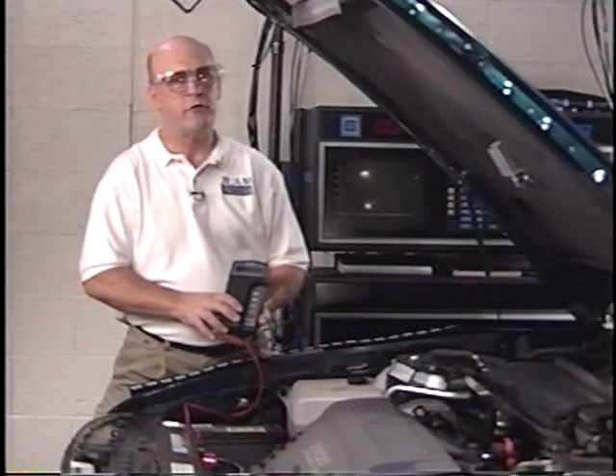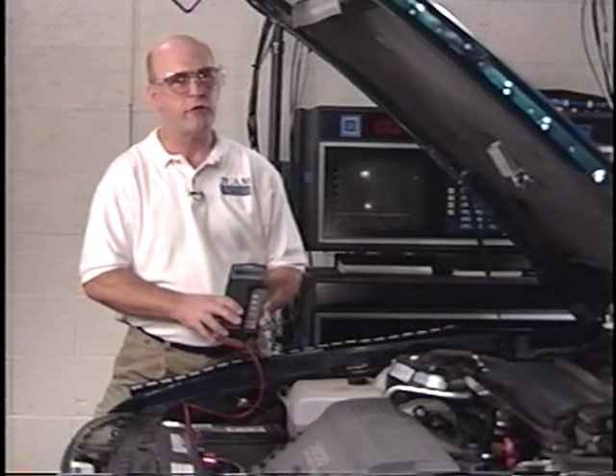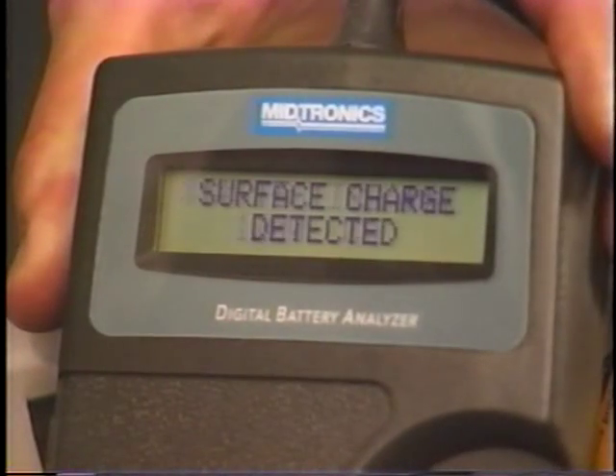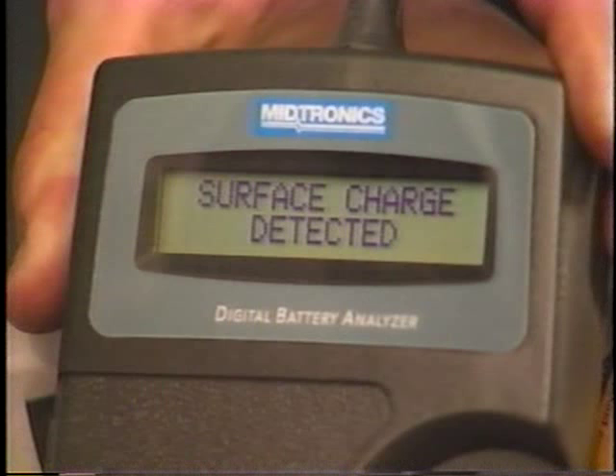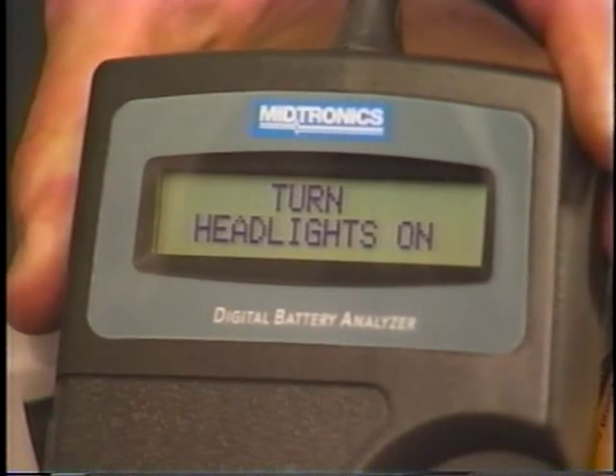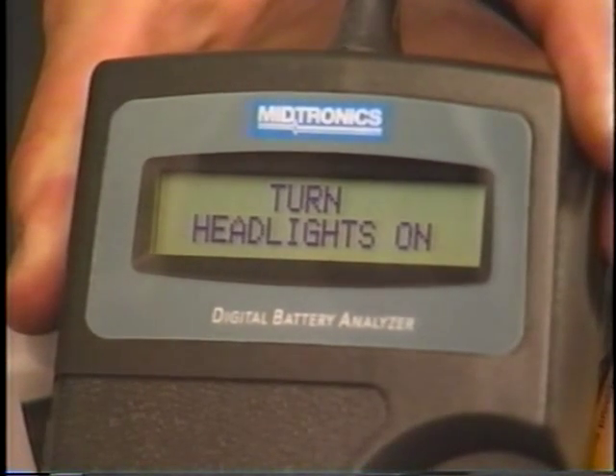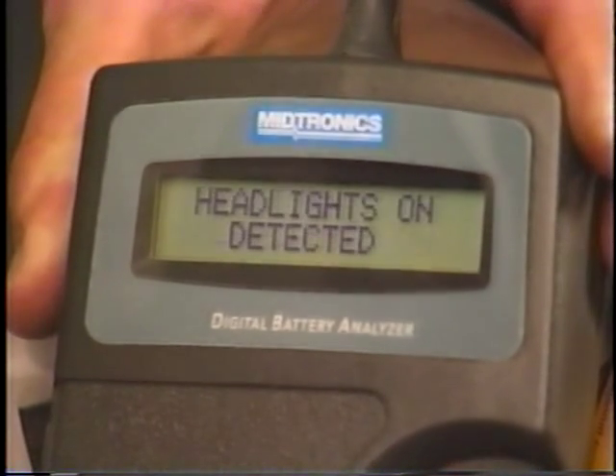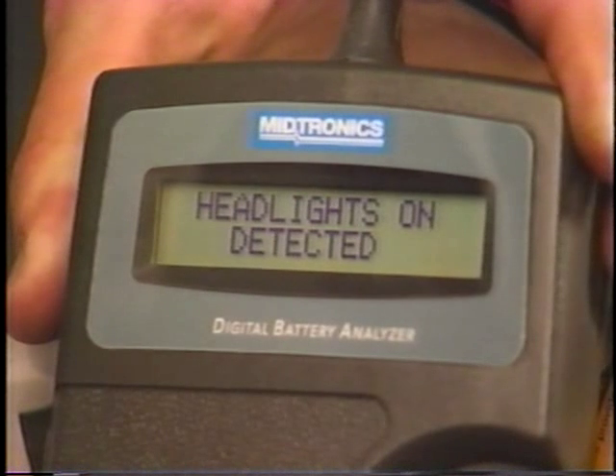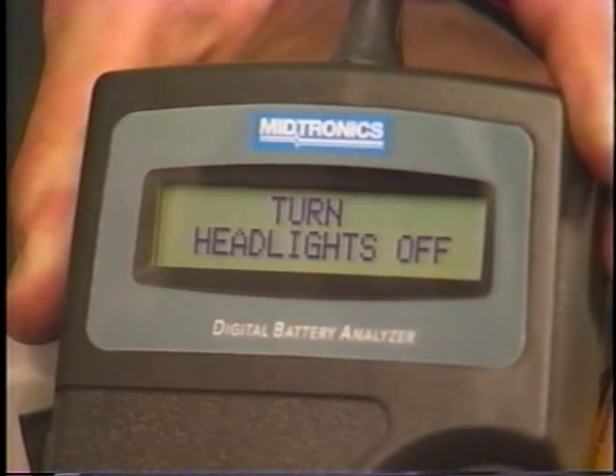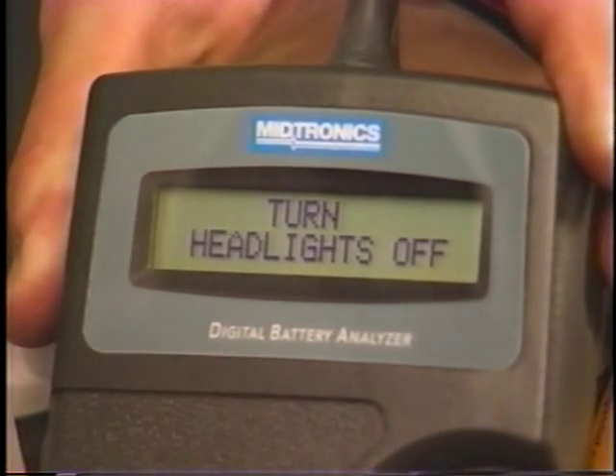One of the test messages you may receive is surface charge detected. That means the voltage is elevated and you'll need to remove the surface charge before proceeding. To dissipate it, the tester will prompt you to turn on the headlights for a period of time. When the message changes to turn headlights off, the unit will automatically retest when the voltage stabilizes.